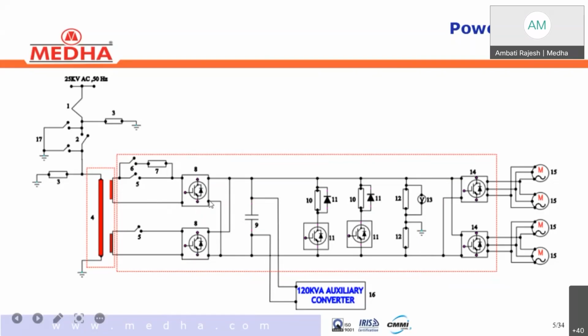Both the line converters' outputs are connected in parallel. The negative is connected here and the positive is connected here, so both outputs are connected to a common DC link. This DC link is always maintained at 1800 volts for normal operation. To suppress any AC ripples available in the DC link, this capacitor bank, the DC link capacitor bank, is provided. The pure DC is then given further to the traction converters.